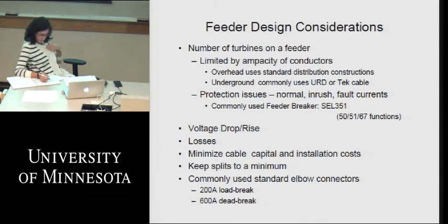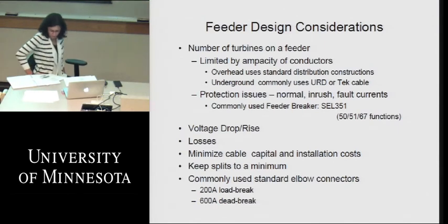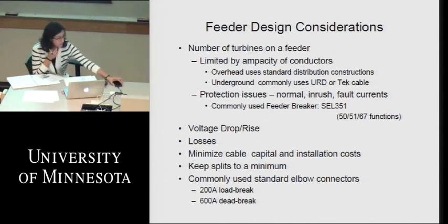But the other thing you've got to consider on the feeder is voltage rise and drop. I mean, underground cables will tend to be capacitive, which will tend to drive the voltages up. Overhead constructions tend to be inductive, which tends to have voltage drop as the cables get longer and longer. But you've got to do this voltage rise calculation to figure out what your voltages are going to be from the wind turbines back to where you're collecting it and connecting them up to the grid. And you've also got to calculate the losses within the grid, the installation costs, and things like that. And of course, we use, again, standard connectors from the distribution industry here at 200 and 600 amp.